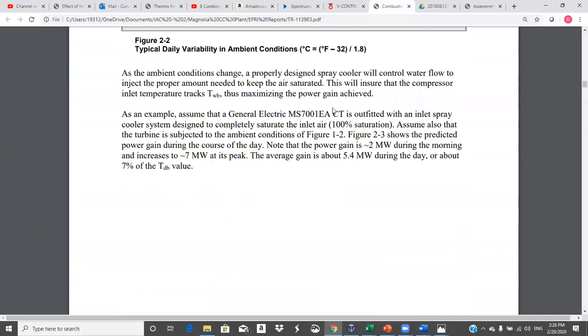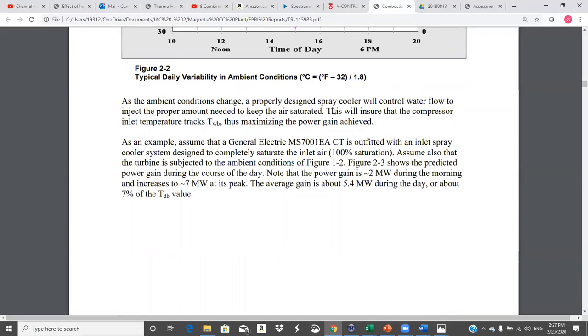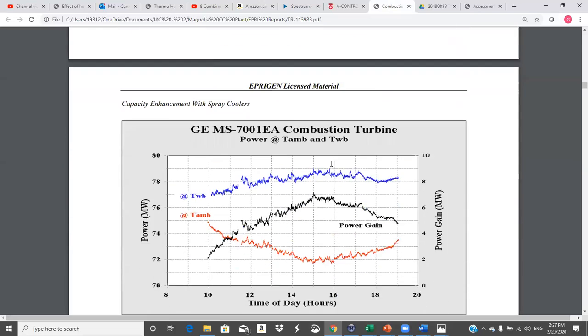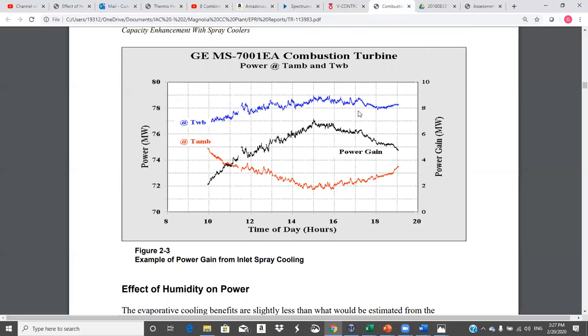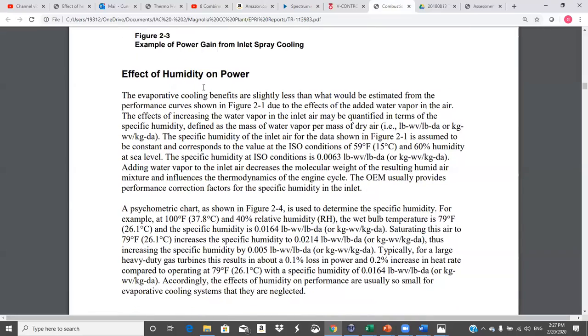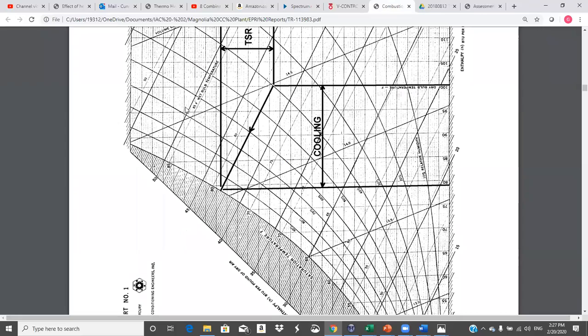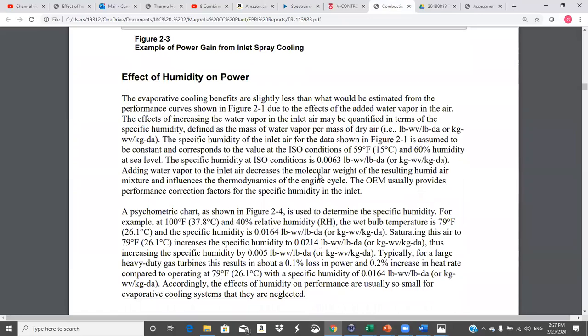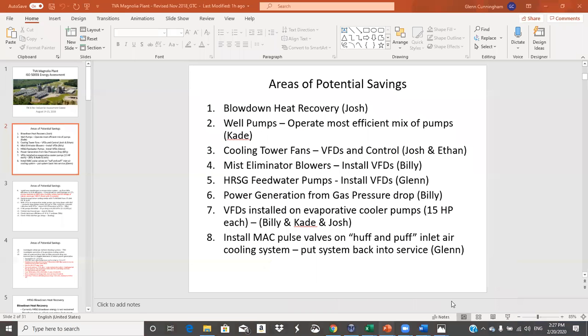Here's another one. What is this one? This may be a different example. Assume this is a GE gas turbine unit, combustion turbine, outfitted with an inlet spray cooler, designed to completely saturate inlet air. Assume also that the turbine is subjected to ambient conditions. So anyway, they've got all kinds of plots of this. But if you go all the way to saturation, you do risk droplet carryover into the first stage of the compressor, which could be a danger. And then they talk about humidity. Humidity has a slight detrimental effect. Anyway, I think that's enough of that. Okay, huff and puff filters.